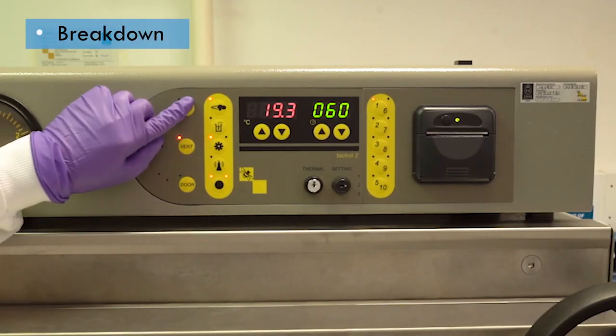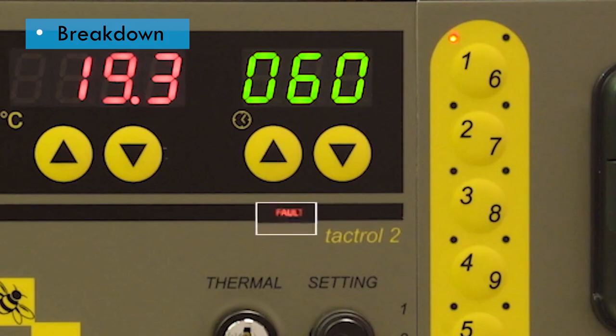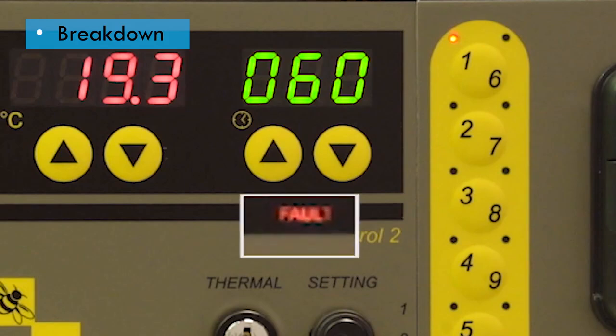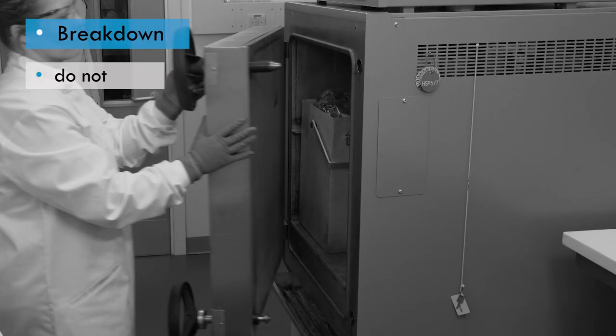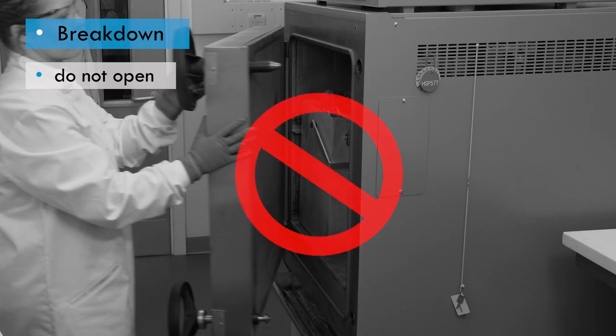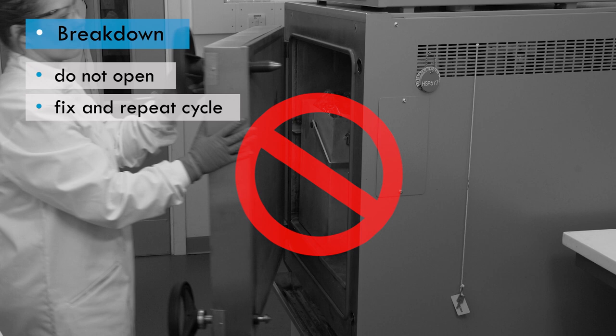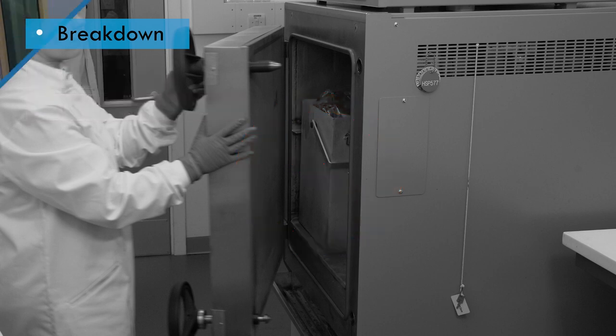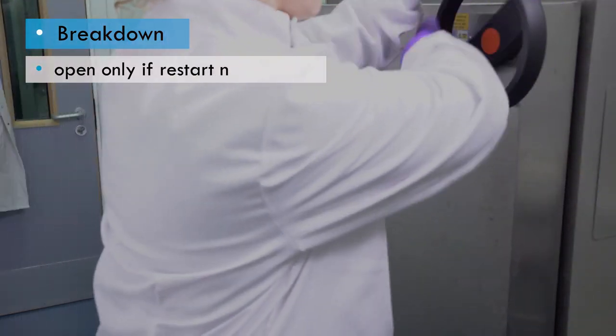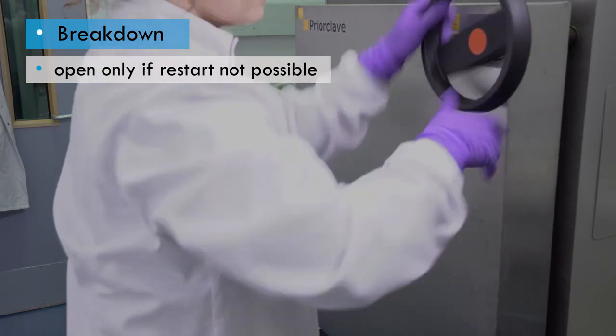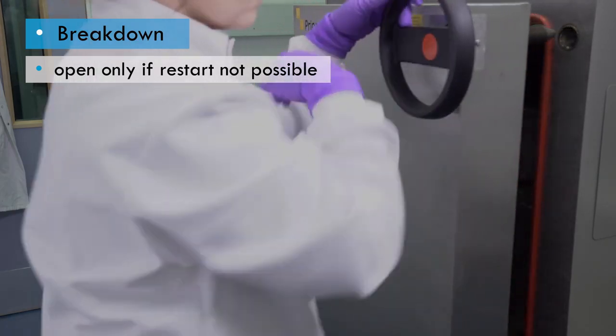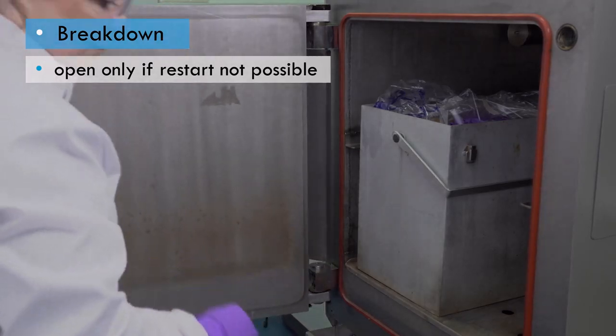If there is a power failure, or if the autoclave breaks down during a sterilization cycle, the autoclave should not be opened straight away. Instead, attempts should be made to fix the autoclave and repeat the cycle. Only if it's not possible to restart should the autoclave be opened and the incompletely autoclaved waste removed.